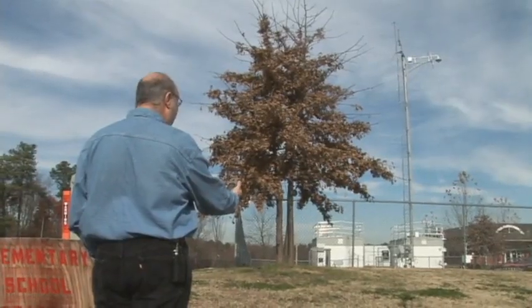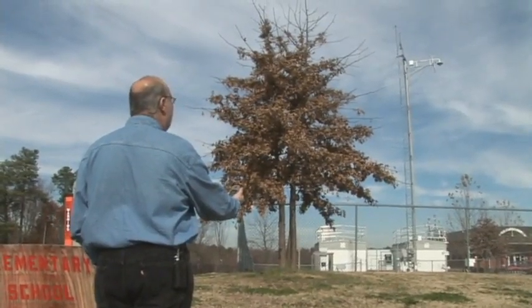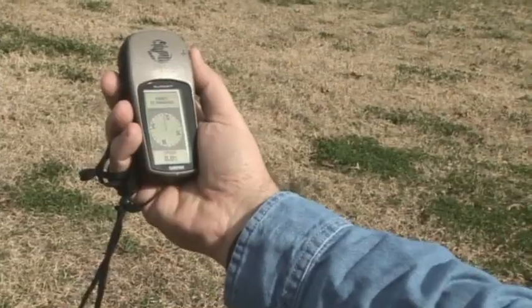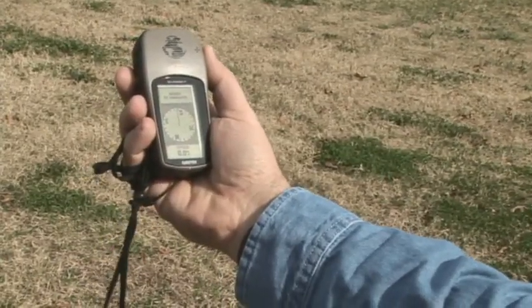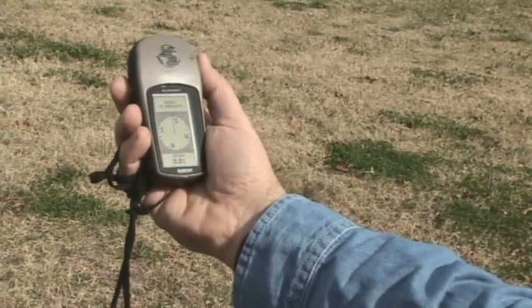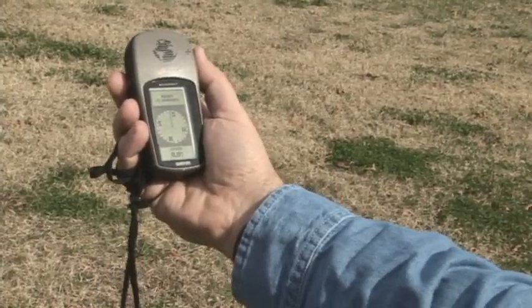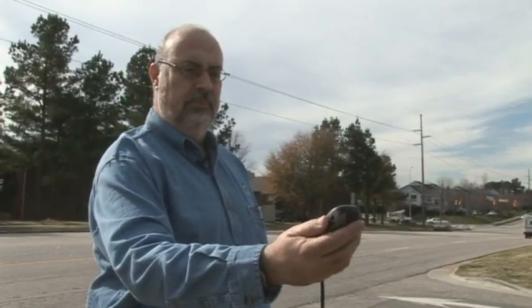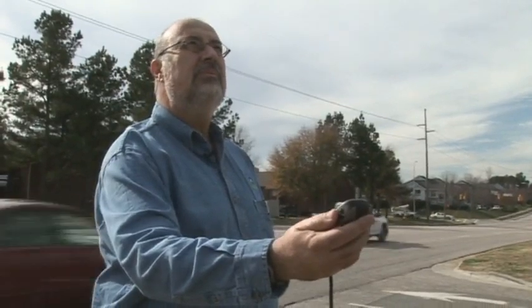Perform the same procedure as before. This value that the GPS displays should be plus or minus 180 degrees of the first value that you recorded. If it is 180 degrees from the first recorded value, you have referenced the instrument boom correctly. At this time, you may now lower the tower.